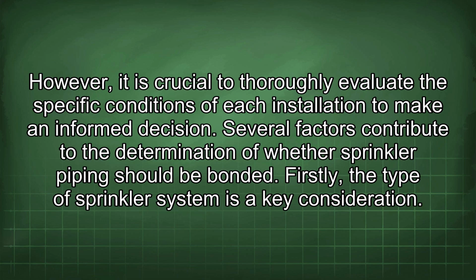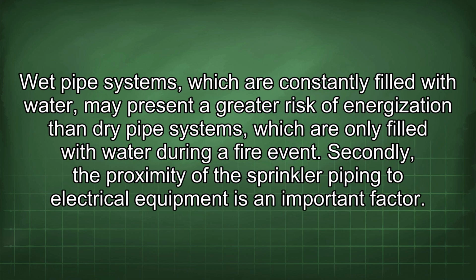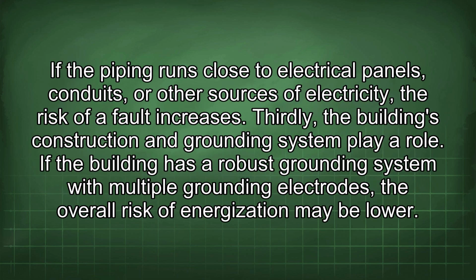Several factors contribute to the determination of whether sprinkler piping should be bonded. Firstly, the type of sprinkler system is a key consideration. Wet pipe systems, which are constantly filled with water, may present a greater risk of energization than dry pipe systems, which are only filled with water during a fire event. Secondly, the proximity of the sprinkler piping to electrical equipment is an important factor. If the piping runs close to electrical panels, conduits, or other sources of electricity, the risk of a fault increases.